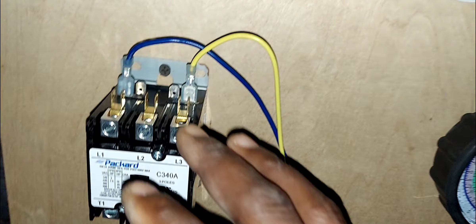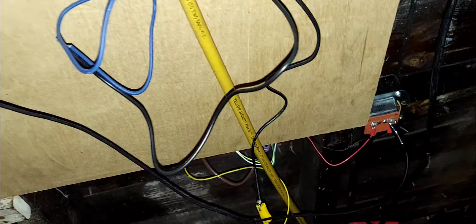So right now it's actually wired, these wires from the thermostat. Oh, come on. The wires from the thermostat are actually connected. So this thermostat is actually doing cooling right now, and my cooling signal is actually coming down. However, okay, just reconnected my common. That's my common right there, 24 volts hot going to my thermostat. So, okay, this yellow wire is connected back here. It's coming out of the thermostat, the cooling signal. Okay, so the cooling signal is coming to this wire right here.